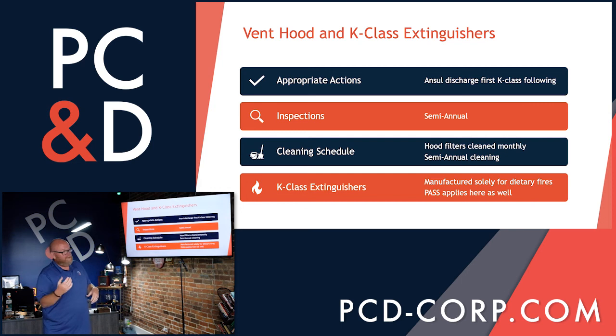And if you're wondering about the fusible link, which we haven't talked about here, but we may talk about later, it's those same fusible links that are used in your attics and used on some of your registers on the ceiling. So anywhere that you have a penetration of a firewall and you've got a fusible link holding open a fire damper, same technology, same principle takes place. If that fusible link gets so hot due to a fire, that fusible link will melt, that damper will close. So the principle of a fusible link we see used quite frequently throughout all of our life safety components.